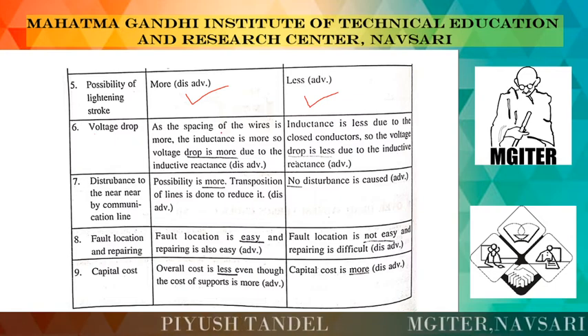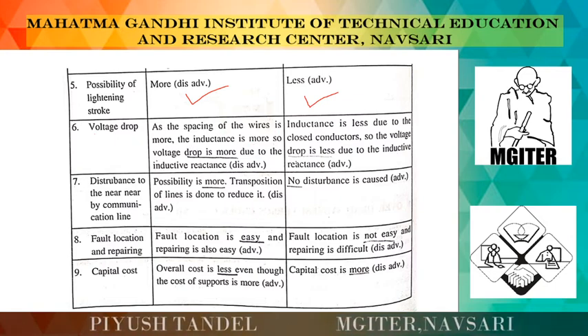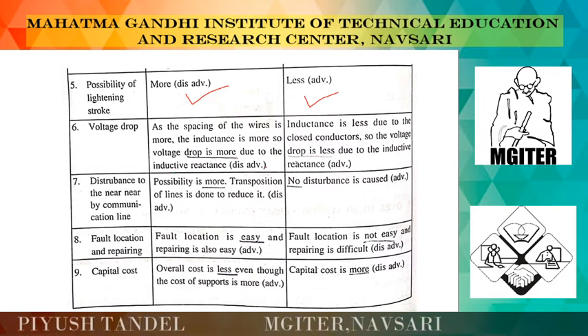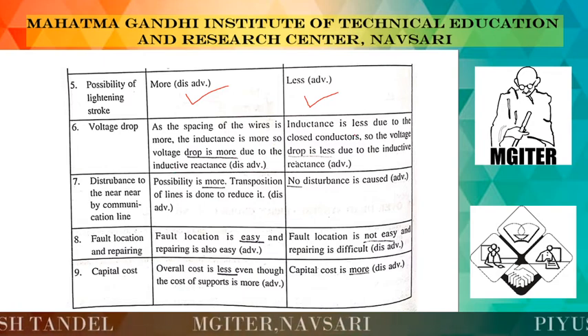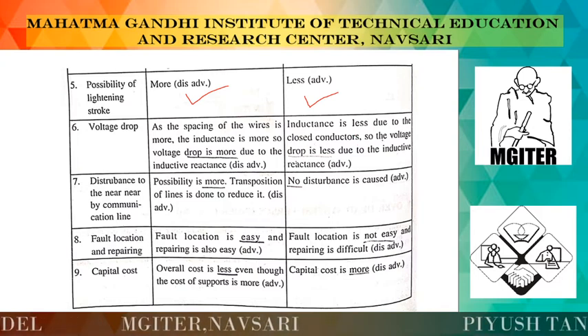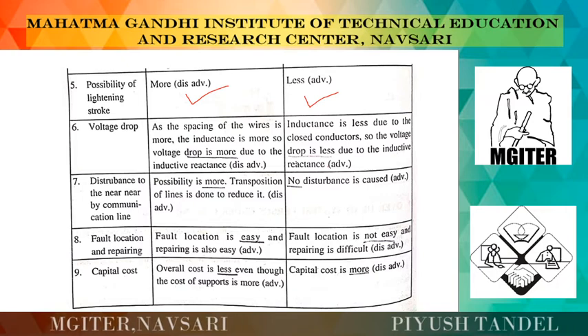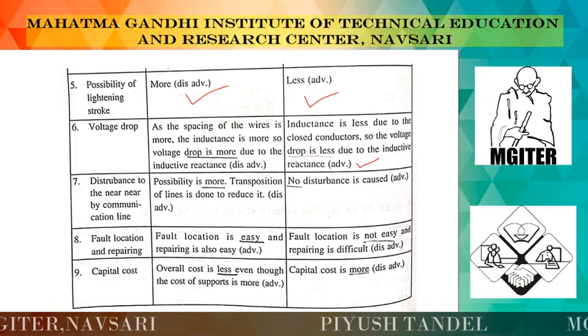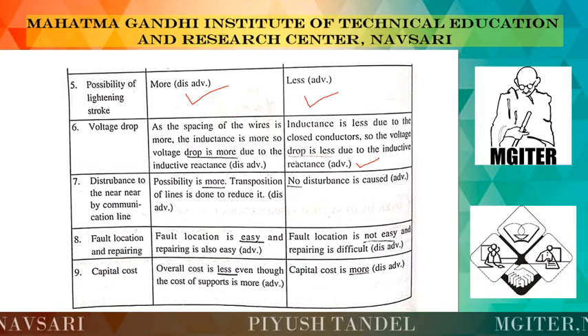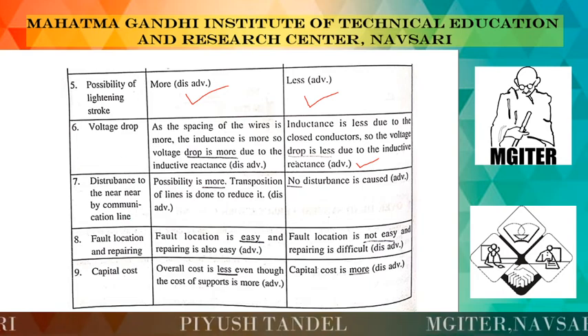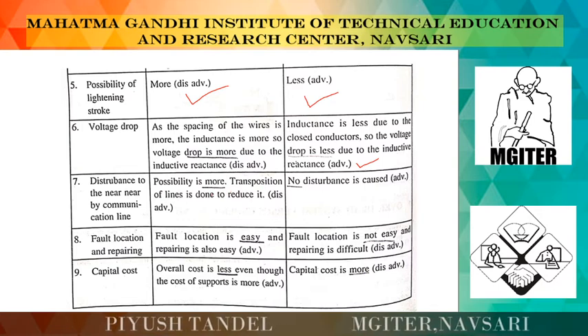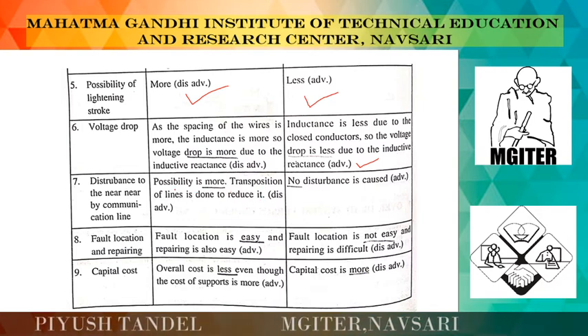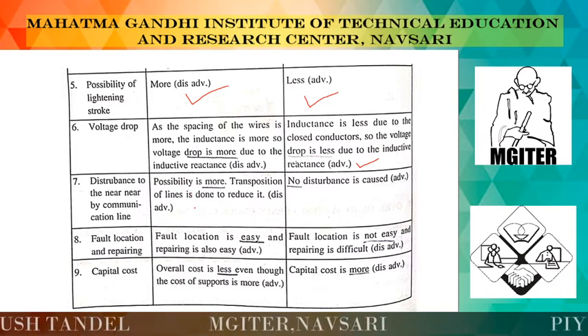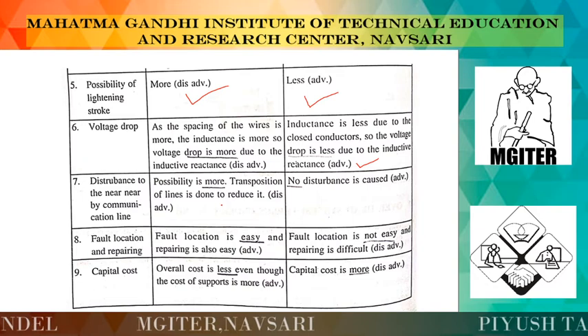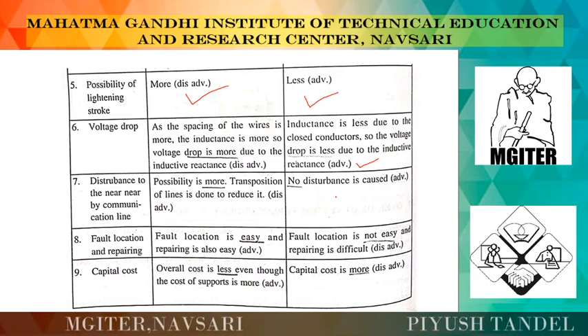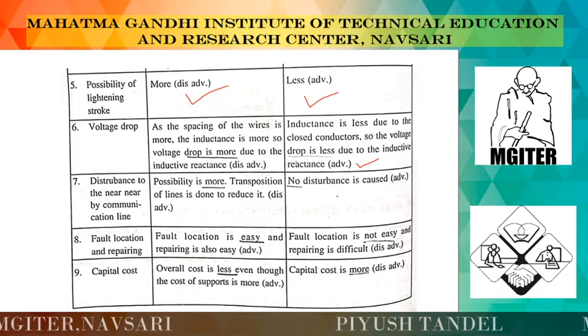Next one is the voltage drop. As the spacing of the wires is more, the inductance is more, so the voltage drop is more due to the inductive reactance. That is the disadvantage of the overhead system, while inductance is less due to the closely spaced conductors, so the voltage drop due to the inductive reactance is much less, and that is the advantage of the underground system. Now disturbance to nearby communication lines: the possibility is more, and transposition of the line is done to reduce it, because the overhead system is going to disturb your nearby communication line, and to reduce that effect we transpose our transmission line, and there is no disturbance caused in underground systems.